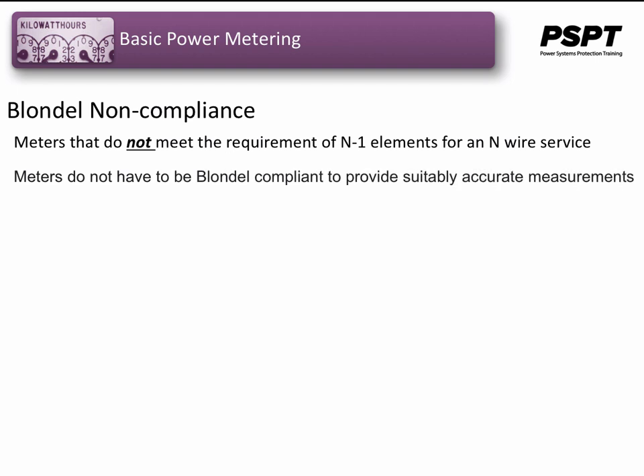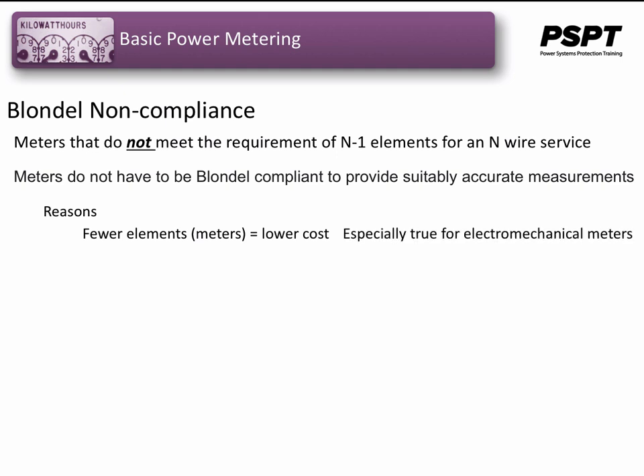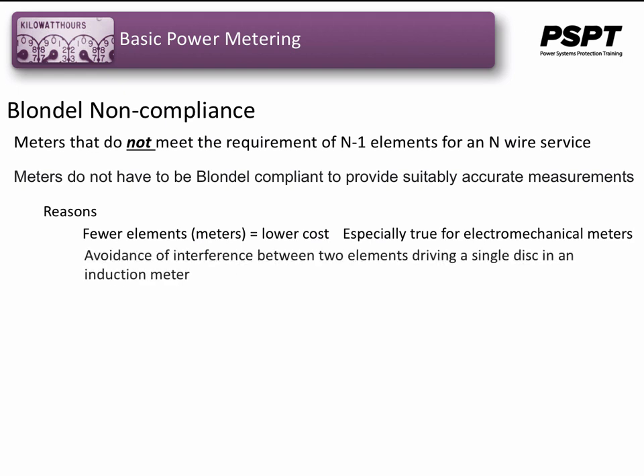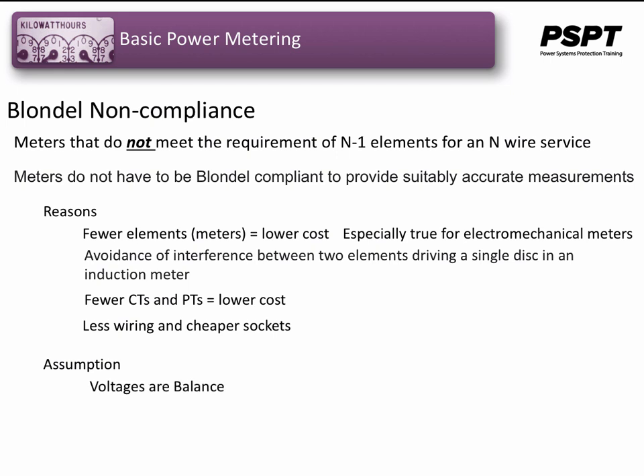The reasons for using meters that are not Blondel compliant, despite the need for stability and accuracy of measurement, are that you'd want to have fewer elements and lower costs, especially true for electromechanical meters. There's an avoidance of interference between two elements driving a single disk in an induction meter. There would be fewer CTs and PTs, and in very high voltage systems, CTs and PTs can introduce a significant cost into the metering system. Of course, there's less wiring, and there are fewer things that can go wrong if there are fewer wires, as well as some savings in not buying the wire. Some of the assumptions that are made, and we've looked at those already, are that the voltages are balanced and equal and 120 degrees apart.